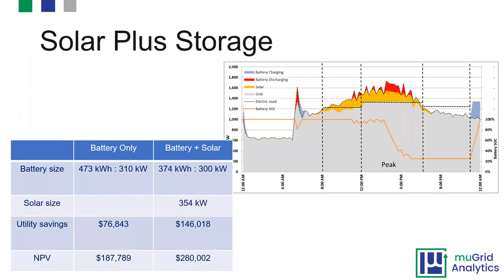You can add solar to this as well. Now you've got solar operating through much of that peak period, providing energy that the battery didn't have to. Storage is very complementary — synergistic with solar — because batteries like those peaky load profiles and that jaggedness. Solar will actually create some of that jaggedness for you, because every time a cloud goes over you get a dip. The battery can smooth out those peaks, increasing the amount of peak shaving without having to add significant energy capacity.